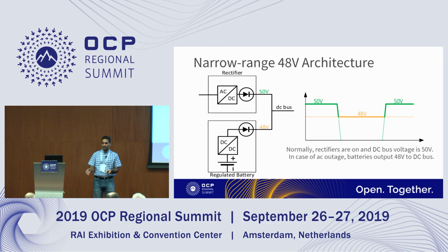The other problem was at the server side: since the voltage is 40 to 60, you cannot use a 60 volt component, you need to go to the next component voltage, which is 100 volt. So all the hot swap controllers, capacitors, switches, MOSFETs normally the next component level is 100, so you have to go to 100. It has both the complexity of the voltage and the current.